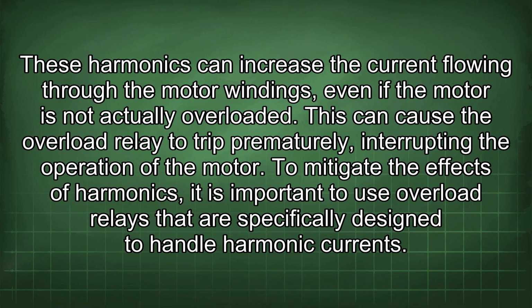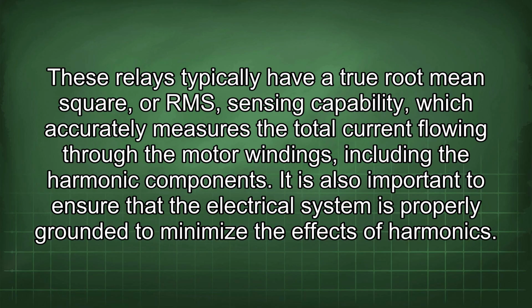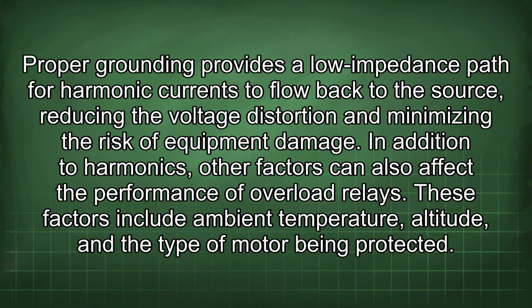To mitigate the effects of harmonics, it is important to use overload relays that are specifically designed to handle harmonic currents. These relays typically have a true root mean square, or RMS, sensing capability, which accurately measures the total current flowing through the motor windings, including the harmonic components. It is also important to ensure that the electrical system is properly grounded to minimize the effects of harmonics. Proper grounding provides a low impedance path for harmonic currents to flow back to the source, reducing the voltage distortion and minimizing the risk of equipment damage.